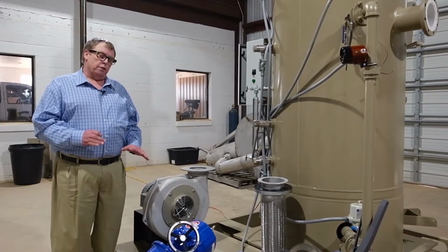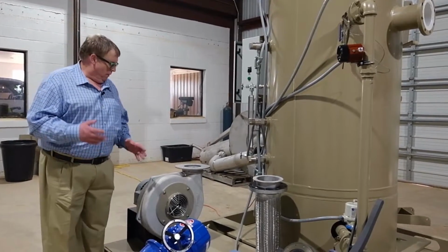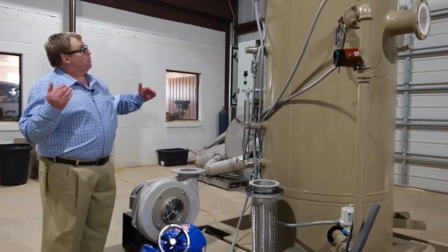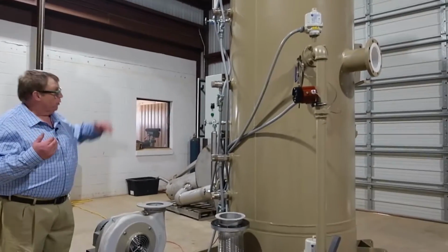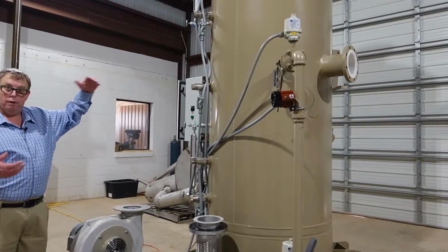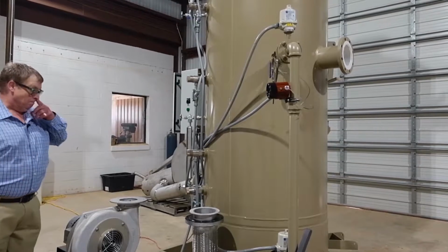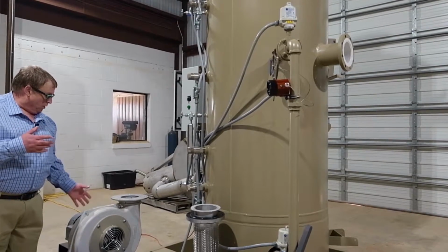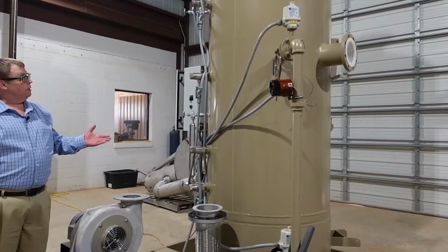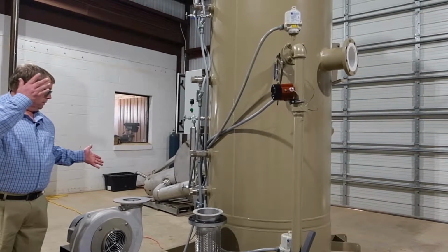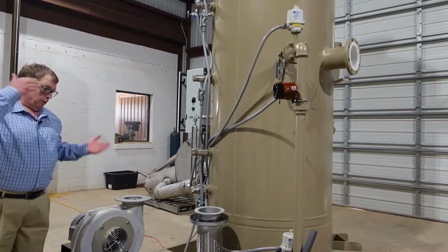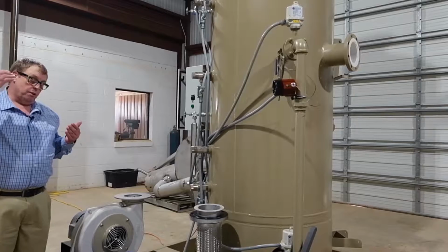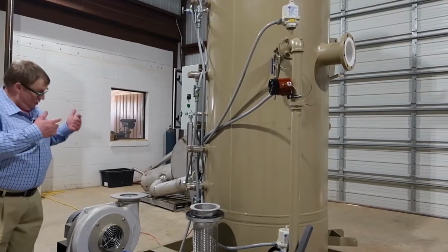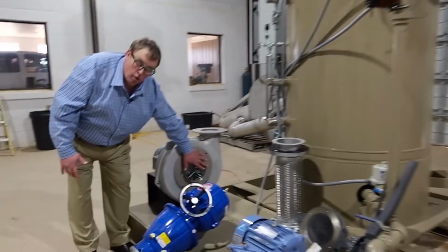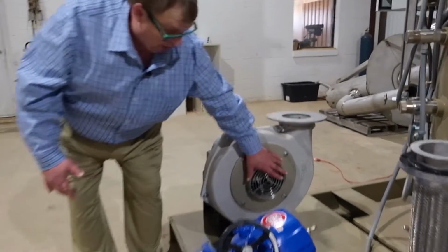This is important in case the blower loses power and you've got perhaps a buildup of heavier hydrocarbons that have lingered in your blower riser. If your blower has lost power and you have these heaviers in the riser, then there's a possibility that these heavier hydrocarbons would ignite and come right out this grill and kind of act as a flamethrower.